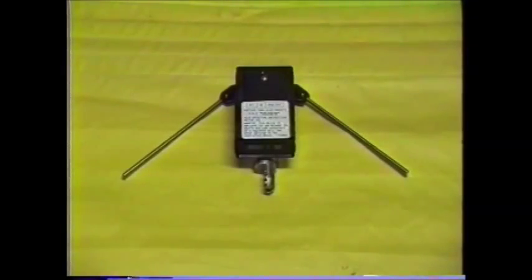The RND has V-shaped electrodes to allow easy contact between the source and load conductors at the top of the regulator. Caution must be used not to connect the RND between one of the high voltage conductors and the neutral or any other grounded surface.